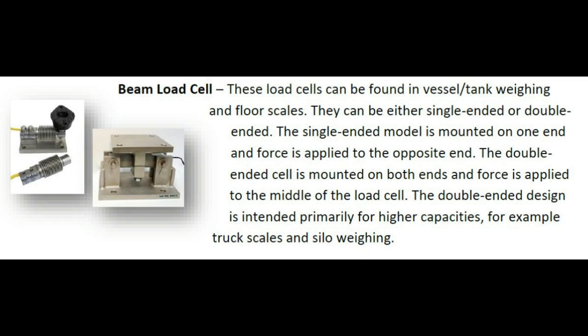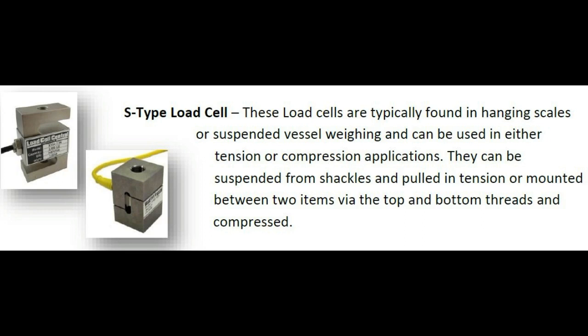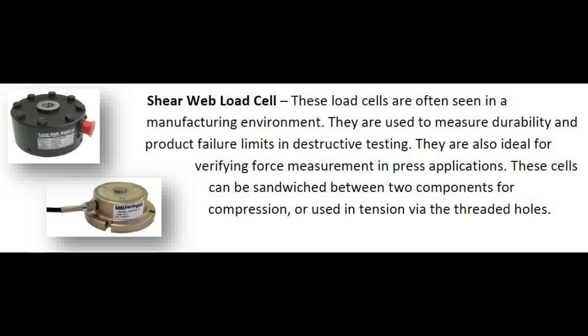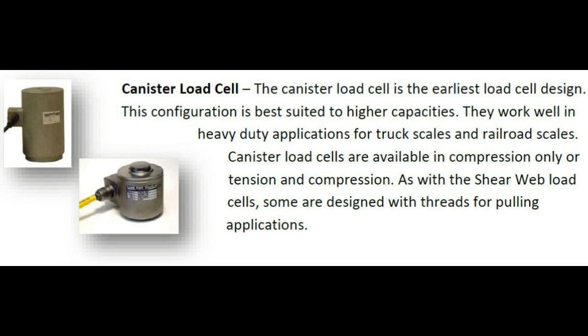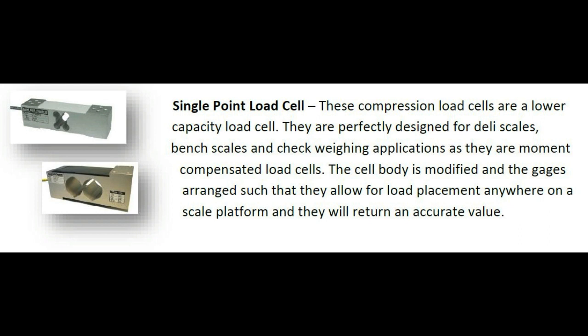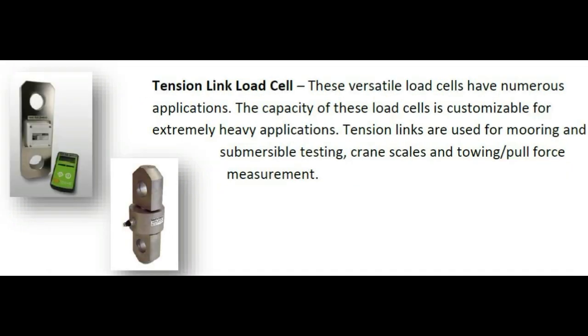Types of load cell: a beam load cell is used for vessel and tank weighing and floor scales. An S-type load cell is for hanging scales or suspended vessel weighing. A shear web load cell is used for verifying force measurement in press applications. A canister load cell is for heavy-duty applications such as truck scales and railroad scales. A single-point load cell is for bench scales and check weighing. A tension link load cell is used for mooring, submersible testing, and crane scales.